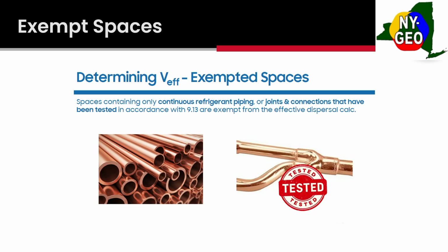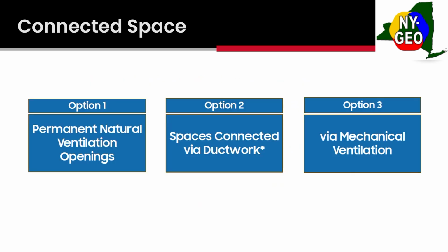All right, so say you get to your Veff and your space is too small. How can you make it bigger? ASHRAE 15 has something called connected spaces, and there's a couple ways you can connect spaces. Number one is through permanent natural ventilation openings, through ductwork, or through mechanical ventilation. So you can take a 1,000 cubic foot area and turn it into 2,000 feet. These are different options you can use to connect your space. And you're going to have to use this a lot more with these VRF systems or any split system where the space is too small. If you can figure out how to expand your volume, then you'll be in good shape.